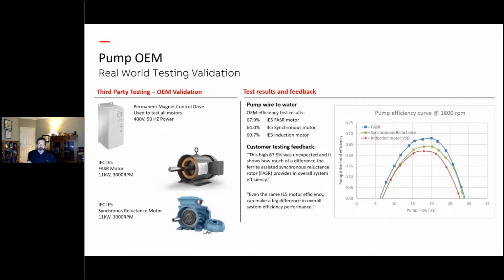So, I can't impart this highly enough. I can tell you the motor does one thing, but until you apply it on the system, that's where your real benefits are. And you can see it here at their pump flow and design point, which was about 80% speed. They were actually kind of shocked in their testing because they thought it'd be close to this IE5 synchronous reluctance motor, and it wasn't.